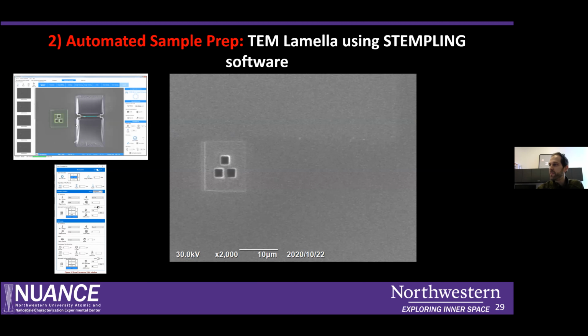So you have a lot of options. You can change the sizes of your lamella, the thickness, the height, the width, you name it. You can change that in the software. I'm going to show you a video of the subsequent steps. These are all automated images that are acquired with the software as well, so you can start your experiment, walk away, and let the instrument do this job for you.